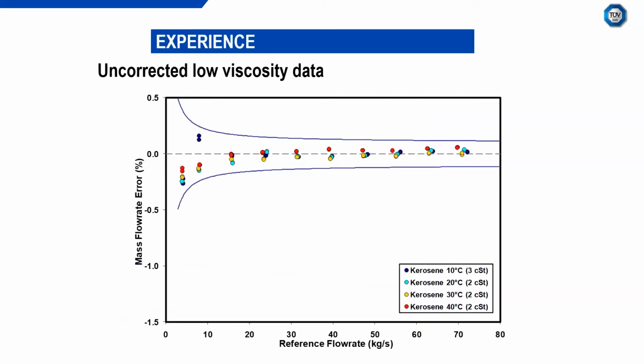Same as before, the y-axis is the mass flow rate error, so that's the deviation between the device under test, the Coriolis meter, and our reference. In this case, it was our gravimetric system. On the x-axis, we have the reference flow rate in kilograms per second. You can see I've overlapped the Coriolis performance specification here. That's the blue lines. You can see that all the data is within specification. We're starting to see zero effects down the bottom there.